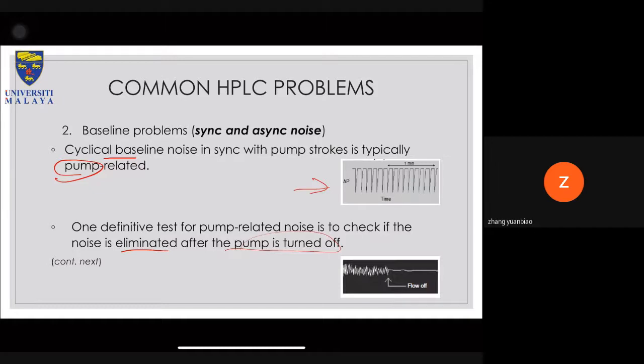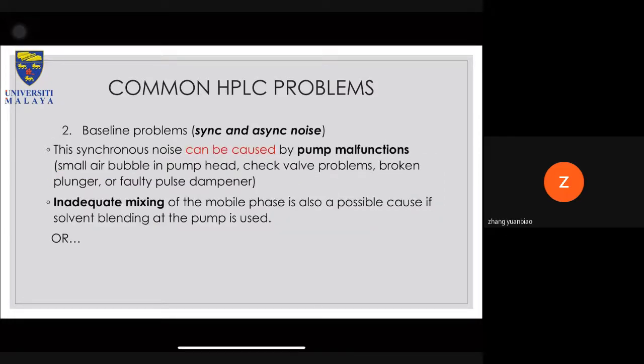All right, synchronous noise can be caused by pump malfunction, small air bubbles in the pump head, check valve problem, broken plunger or piston, or faulty pulse dampener. Inadequate mixing of mobile phase is also a possible cause if solvent blending at the pump is used. Okay, or asynchronous detector noise can be caused by electrical sources, such as ground loop problems, power voltage fluctuation, or electrical shielding problems, and so on and so forth. So this is more difficult to diagnose and remedy. And normally, once you have eliminated all the other problems, you will definitely just call a technician from the manufacturer to actually come and look at your system.